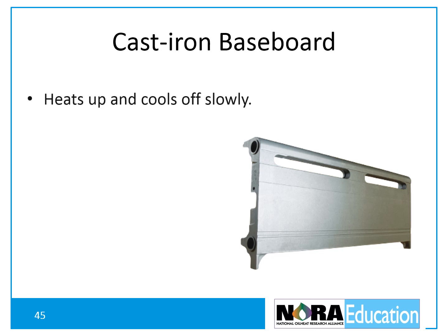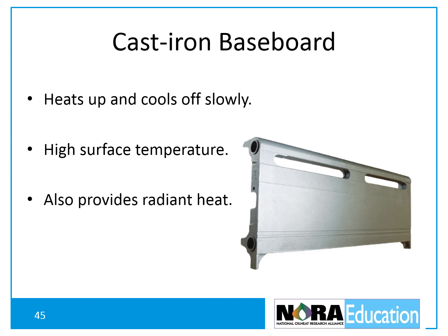Cast iron baseboards heat up slowly and cool off slowly. Surface temperatures are high and there are no protective enclosures. Cast iron baseboards also provide radiant heat because the large mass of iron stays hot after the circulator shuts off and slowly releases energy into the space.